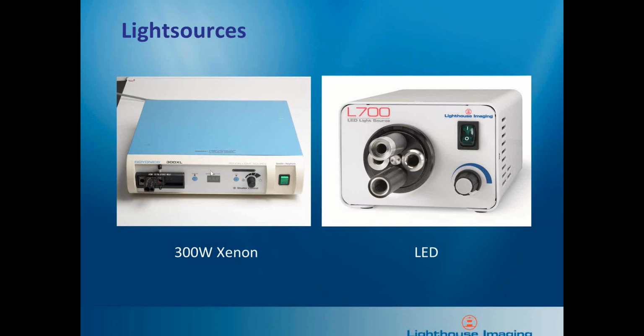Both of these light sources, you'll see, have multiple interfaces. The Smith & Nephew source shown on the left here, the Dyonics, has a little sliding bar with 4 different interface ports on it. And the Lighthouse L700 has probably a little more common turret type system where each of the different brands of cables can be hooked into it just by rotating this turret to different settings. That's a key point that we'll get to with the EndoLume: each of these different settings has very, very different optical characteristics if you don't interface with them the same way that the cables do. When you use the correct cable or a tool such as the EndoLume, the interface is very consistent. If you try to measure these outputs with something more like a lux meter, they are very, very different optical characteristics from one to the other.